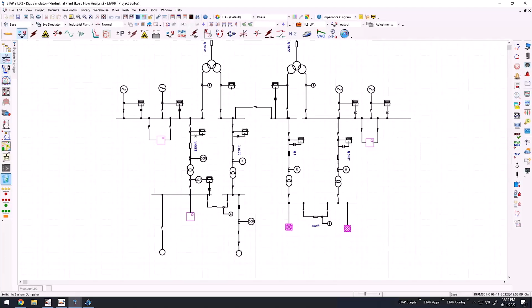In this demo, we can also evaluate the effect of suddenly taking a generator out of service. I will open the circuit breaker of the generator and run a load flow simulation. We can observe that taking this action will cause alarms. As you can see from the alarms, the transformer XT2 will be overloaded.